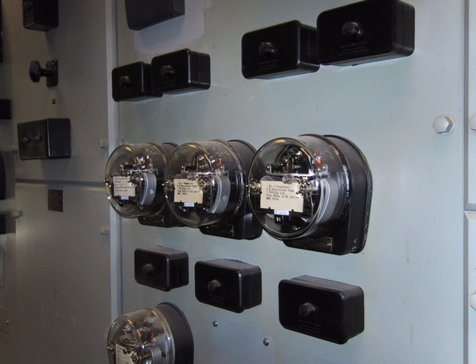During a fault on the transmission line, the fault current increases and the voltage at the fault point decreases. The V-I ratio is measured at the location of CTs and PTs. The voltage at the PT location depends on the distance between the PT and the fault. If the measured voltage is lesser, that means the fault is nearer and vice versa. Hence the protection is called distance relay. The load flowing through the line appears as an impedance to the relay, and sufficiently large loads, as impedance is inversely proportional to the load, can lead to a trip of the relay even in the absence of a fault.